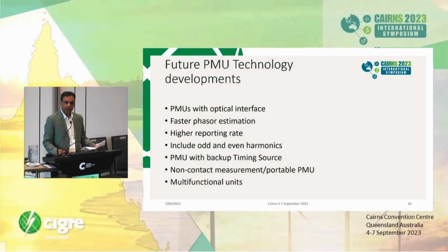We all know how critical GPS time synchronization is for PMUs. So PMUs rely completely on the GPS. So any loss of GPS signal can render synchronized measurement-based applications meaningless. Equipping PMUs with alternative or backup timing source can be an effective solution for reliability improvement.